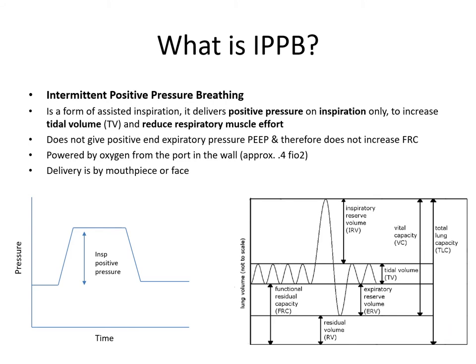Let's remind ourselves what IPPB is — Intermittent Positive Pressure Breathing. This is a form of inspiration delivered through positive pressure on the in-breath, impacting on tidal volume and reducing respiratory muscle effort. It's different to PEEP and doesn't influence FRC. With the Bird specifically, it gives us 40% oxygen from the wall and can be delivered through a mouthpiece, or sometimes a face mask, although most of the time we use a mouthpiece. As you can see demonstrated from the graphs, it influences tidal volume and not FRC, which is directly related to PEEP.